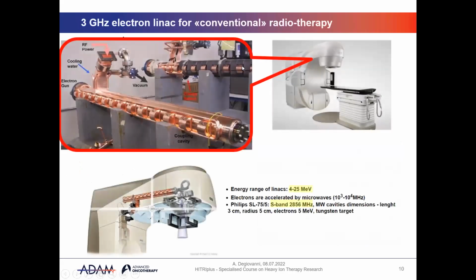Well, if you look at conventional radiation therapy, there are more than 10,000 machines used daily in hospitals for radiation therapy, and they look something like this. If you look inside, there are these types of copper tubes, basically stacks of accelerating and coupling cells, about 1.5 to 2 meters long, that are used to accelerate electrons up to an energy in the order of 4 up to 20 MeV, 25 really at maximum, allowing the electrons to hit a target and generate a photon X-ray radiation field. And all these machines work at this 3 gigahertz frequency, which was the first frequency used to produce also the first research LINAC at Stanford University in the 50s.